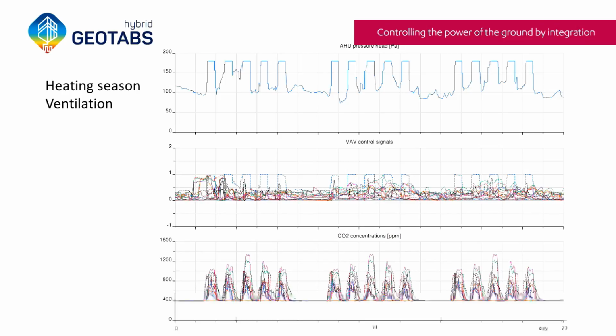This is the same period of the year, where we focus more on the ventilation part of the model predictive control — I haven't gone into detail yet, but we also control the air handling unit. Here it's important to note there's a CO2 concentration limit at 1,000 ppm, and you see we go over this limit. That's not a fault of the MPC — it's simply because in the simulation the ventilation system is undersized, and not a fault of the designer either; we just set the CO2 gains very high.